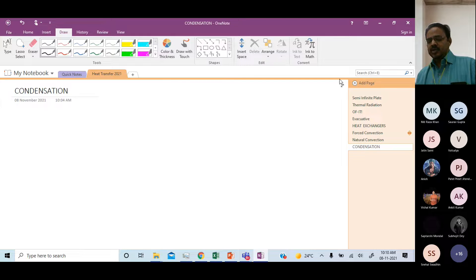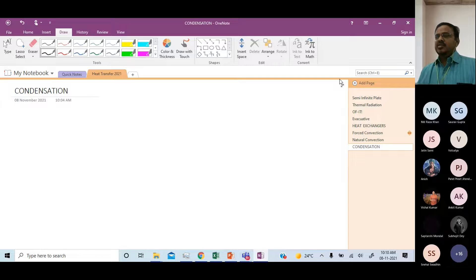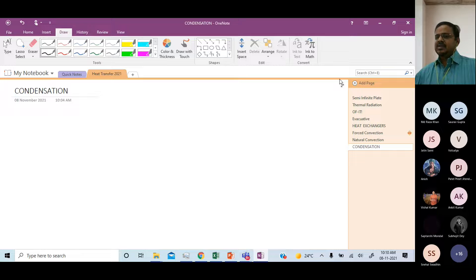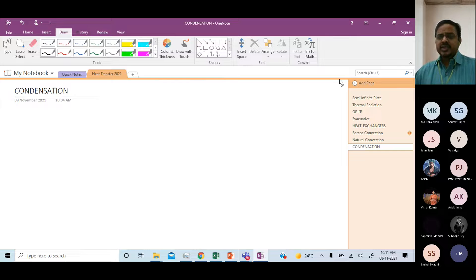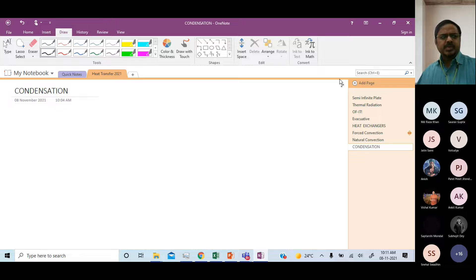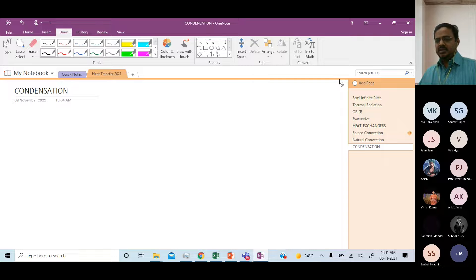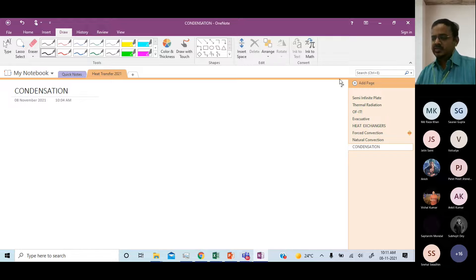In many ACs, looking at the remote or control panel, you'll find a 'dry mode.' What it does is sense the dew point and reduce temperature to that level, so the air you get inside is dry but not as cold. That's why in humid places like Kharagpur, Chennai, Kolkata, or Mumbai, an air-conditioned room is very comfortable not because it's cold but because it is dry. The dry air comes from the moisture in the air condensing on the refrigerant tubes.